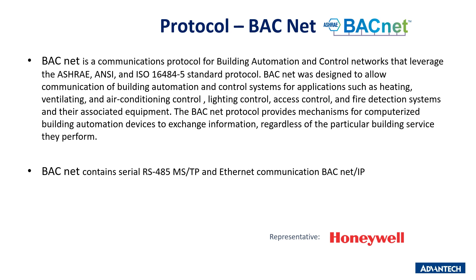BACnet is a communications protocol for building automation and control networks, leveraging the ASHRAE, ANSI, and ISO 16484-5 standard protocol. It was designed to allow communication of building automation and control systems for applications such as heating, ventilating, and air conditioning control, lighting control, access control, and fire detection systems. The BACnet protocol provides mechanisms for computerized building automation devices to exchange information regardless of the particular building service they perform. BACnet supports serial RS-485 MS/TP and Ethernet communication via BACnet/IP.